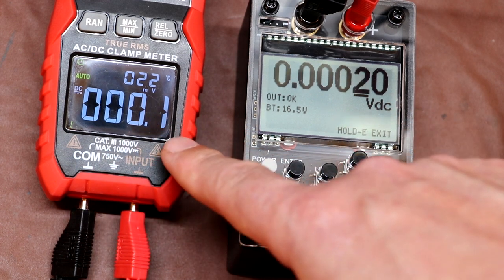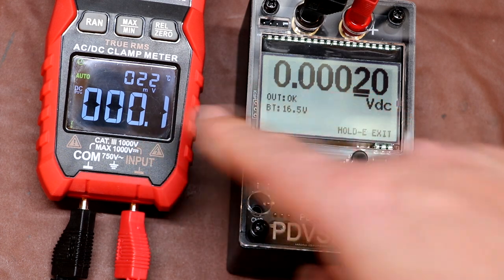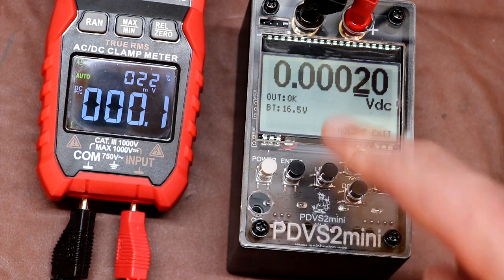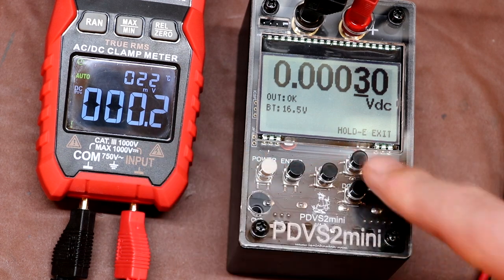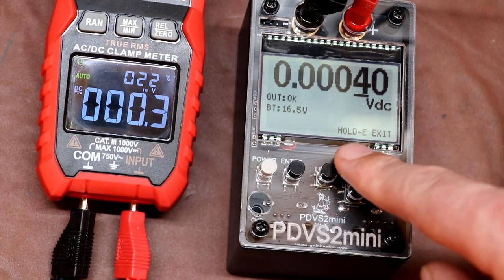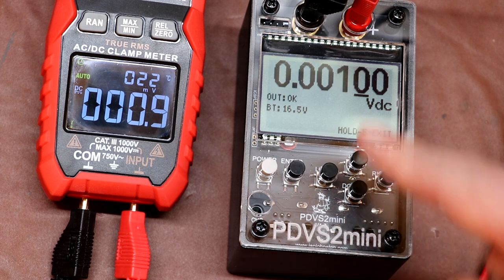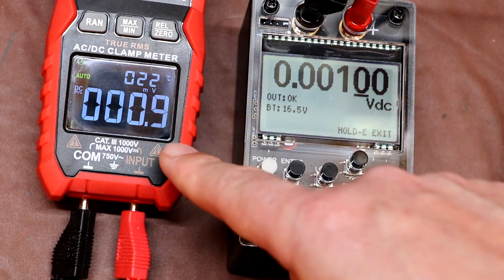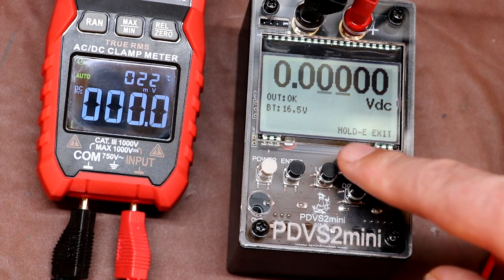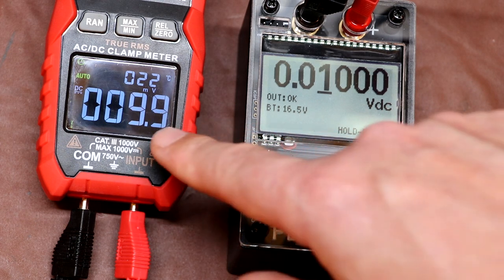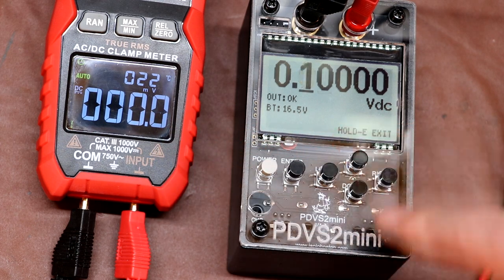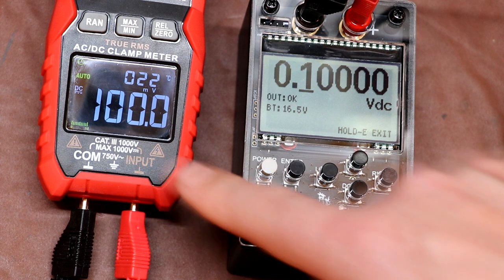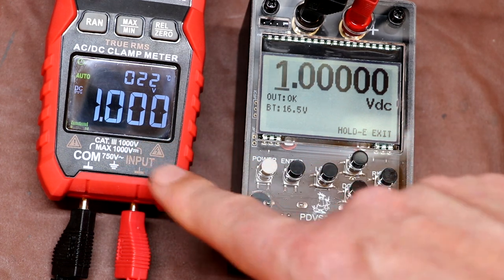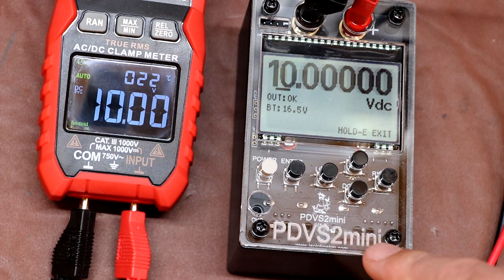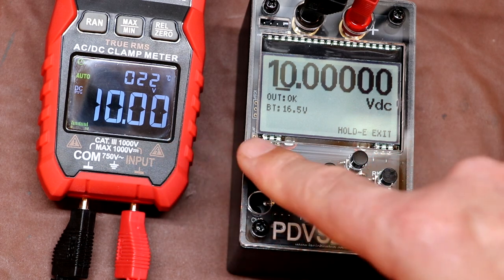Okay, and it has now started to read, so the measurement is within just a couple of counts. Let's increase that. Again, within 3 counts. And with 1 millivolt set, we are within 1 count. Let's try 10 millivolts. Again, within 1 count. 100 millivolts. Spot on. 1 volt, also spot on. And at 10 volts, also spot on.